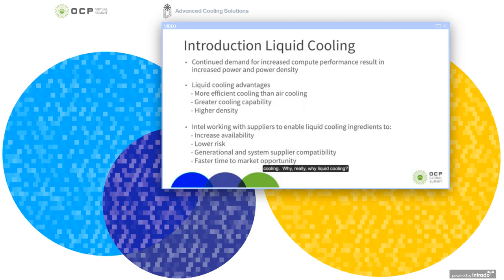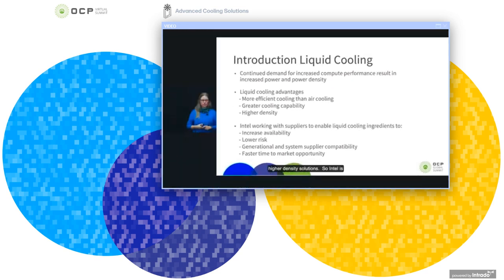Why liquid cooling, right? It's really because we have a continuous demand for increased compute power. And with that also comes increased power and power density of the components themselves. And in order to be able to cool them and meet the thermal requirements, we need more efficient cooling solutions than air cooling. And one of those cooling solutions is liquid cooling, because it allows for that greater cooling capability as well as higher density solutions.